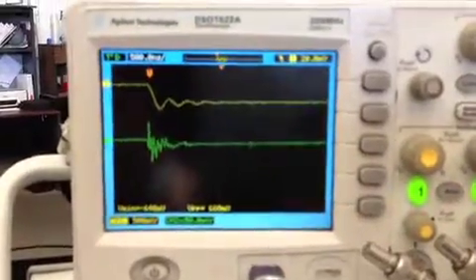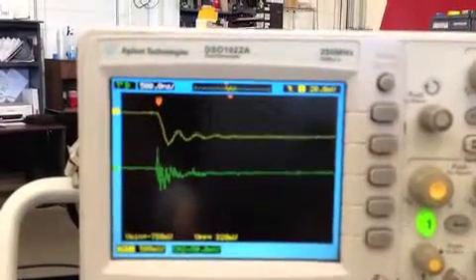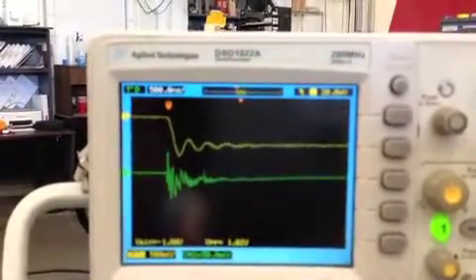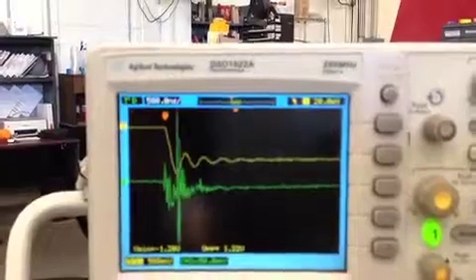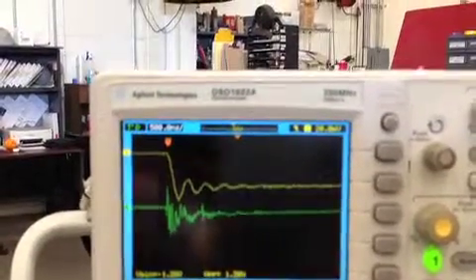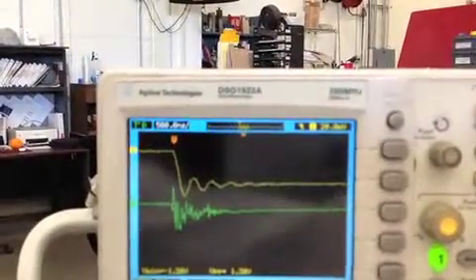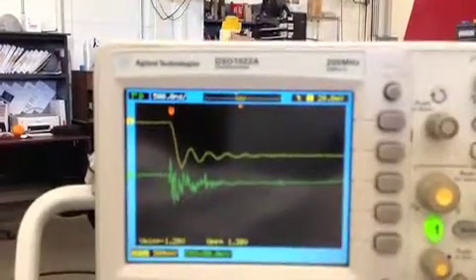And here she's going to raise the voltage until we see a crackling over. There we go. Now, that was the indication that we've reached the level at which partial discharge is occurring.